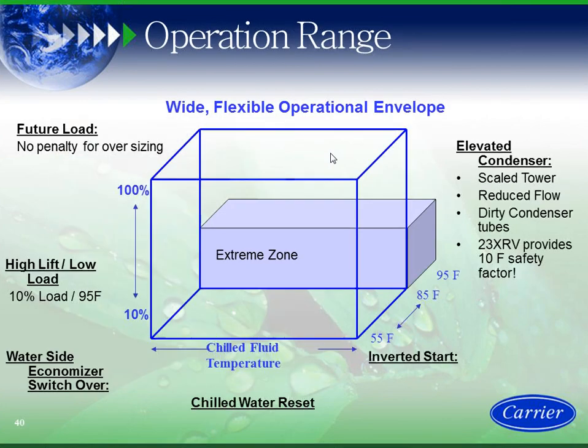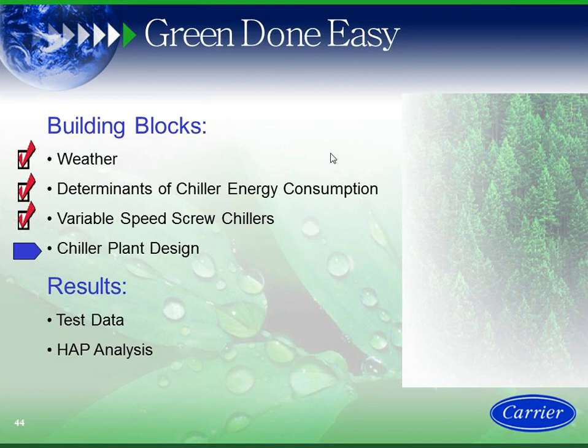The wide operating range, basically the operating range is everywhere in that block and the extreme zone. So I could run with cold condenser water, I can do inverted starts, I could run at low load, high tower. This machine, there's no other chiller in the marketplace that has the operating envelope that this machine does. So we kind of wanted to talk a little bit about the 23XRV and show you how I implemented it into a chiller plant design.